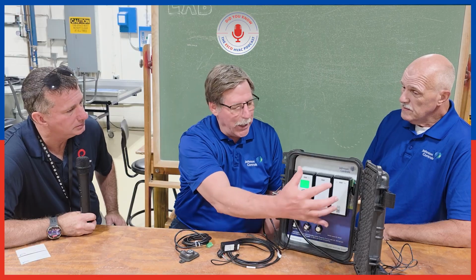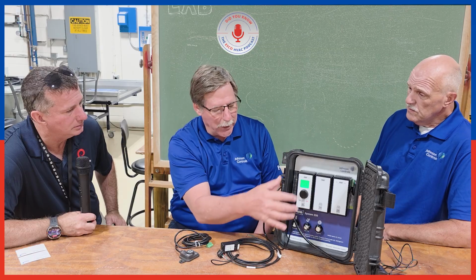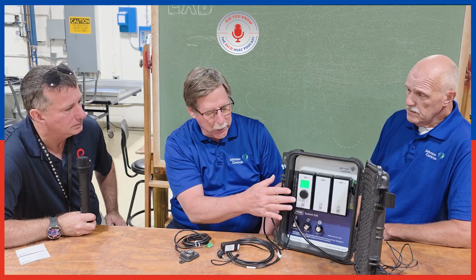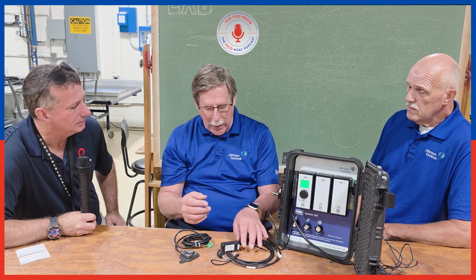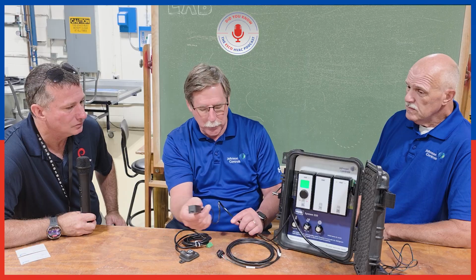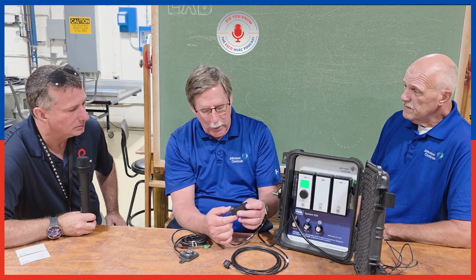Do I have my A2L sensors configured correctly? And do I have my controller configured correctly? So we have a function here called test lock, which doesn't lock the controller down permanently. It can be unlocked. And then I can simulate here with a little tool that we have. This has a program in it, and so I'm simulating a sensor.